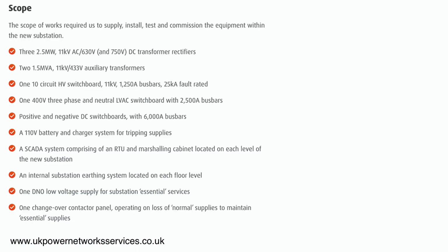There are 3 2.5 megawatt DC transformer rectifiers which convert 11 kV AC into 630 volt DC to run the trains. 2 11 MVA transformers step down 11 kV to 430 volts, used for station lighting and power. There's also a whole bunch of switchboards, a SCADA system, and a few other systems listed here.